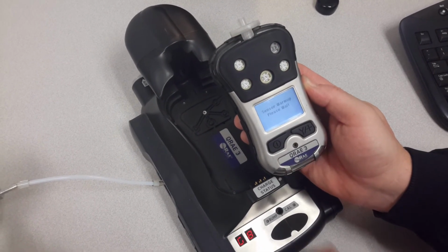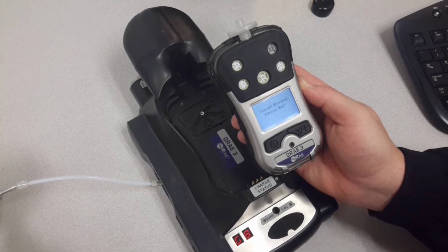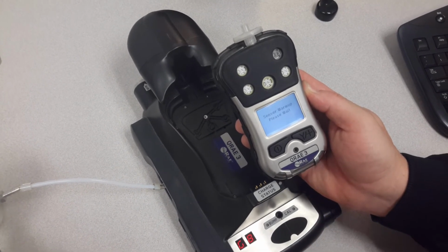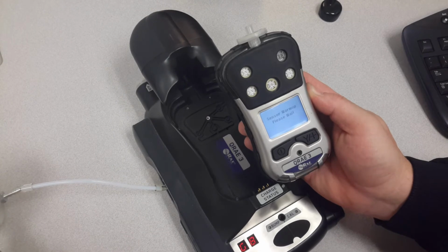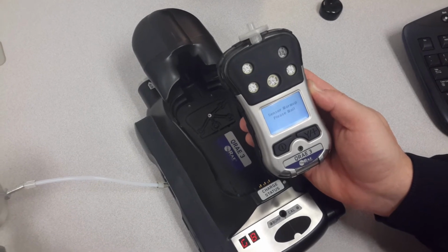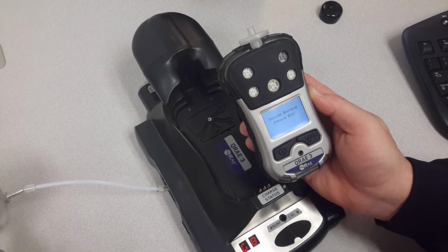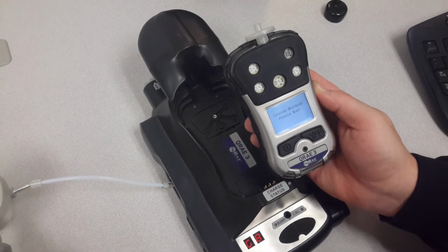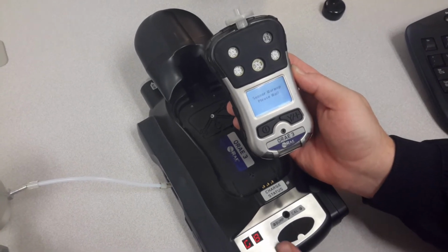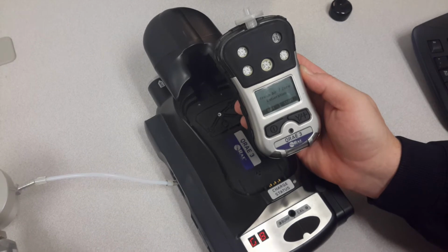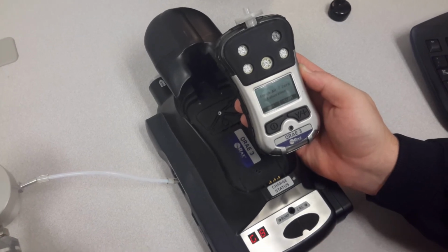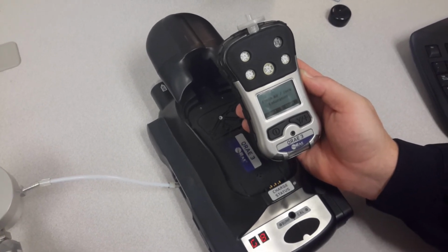It just says sensors are warming up. You saw the red LED indicators, and the alarm went off. And it should have returned to normal mode here in a few seconds. So with this Cradle, we did the bump test, but for the calibration, it's the same exact thing. When you press calibration, the only thing is the test takes a little bit longer.